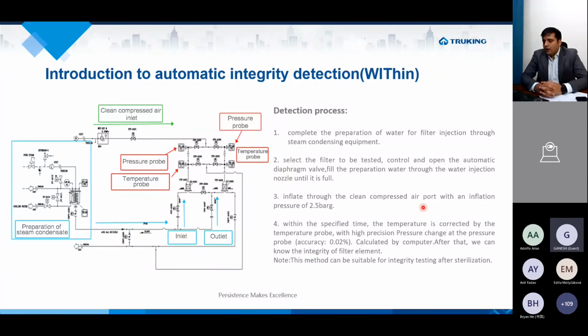Perfect. Talking about the automatic integrity detection in the WIT test, we have pressure probes. We have the complete preparation of water for filter injection through the steam condensing equipment employed for the integrity tester. Then we select the filter to be tested, control and open the automatic diaphragm valve, and fill the preparation water through the water injection nozzle until it's full. Then inflation is done through compressed air at 2.5 bars. Within the specified time, as we said, the WIT test is linked with the P naught V naught equals P1 V1 formula, and pressure decay is very important in this domain.